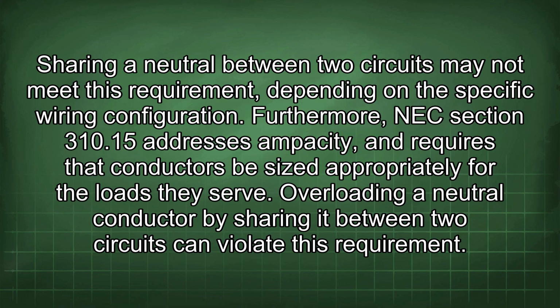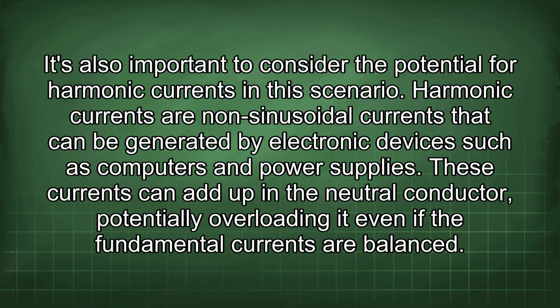Furthermore, NEC section 310.15 addresses ampacity and requires that conductors be sized appropriately for the loads they serve. Overloading a neutral conductor by sharing it between two circuits can violate this requirement. It's also important to consider the potential for harmonic currents in this scenario. Harmonic currents are non-sinusoidal currents that can be generated by electronic devices such as computers and power supplies. These currents can add up in the neutral conductor, potentially overloading it even if the fundamental currents are balanced.